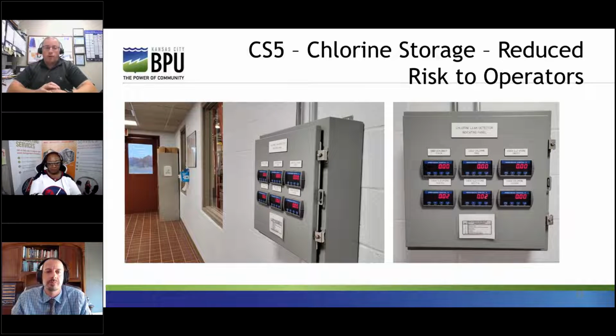This was the solution of the problem. We extended each chlorine leak detector's display to an isolated hallway just outside of the chlorine storage room and in one large panel. We extended each specific leak detector to the SCADA system with a 4 to 20 output through the display so that operators can see the level of chlorine in parts per million that the detector is showing in alarm. Operators no longer need to enter the room, and that's a huge improvement in safety. And everyone is very happy with this solution.